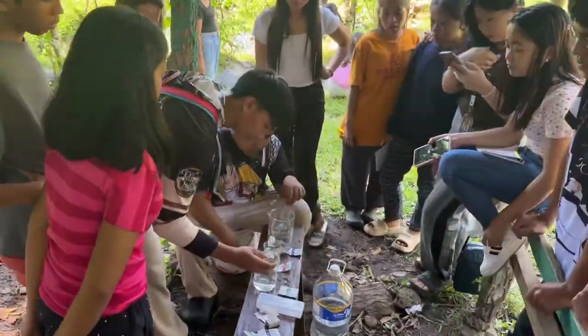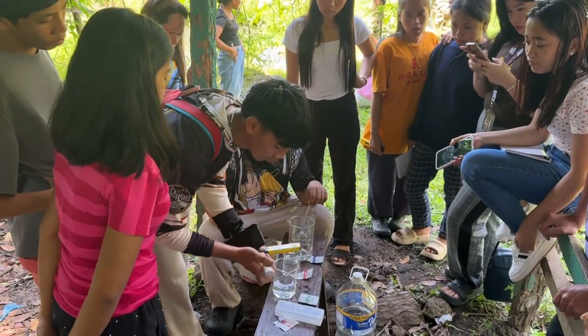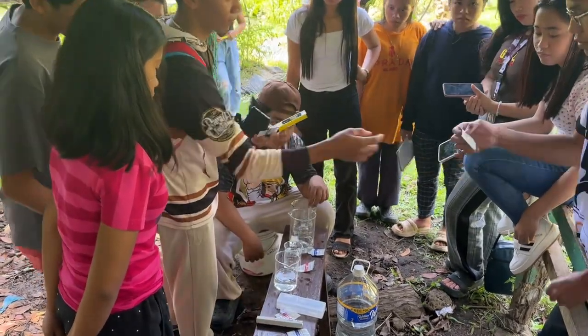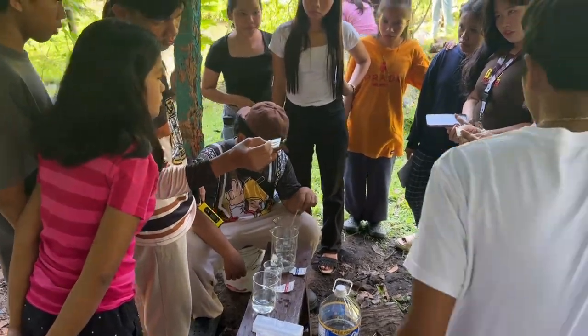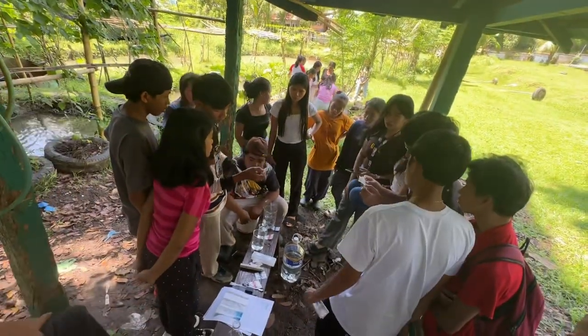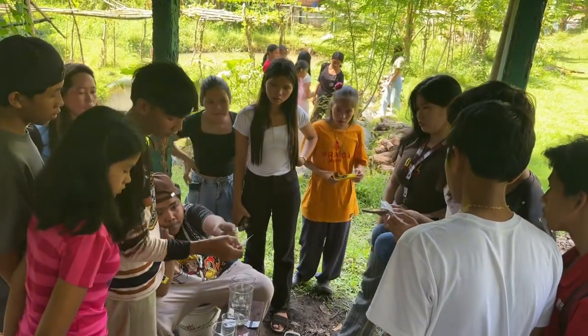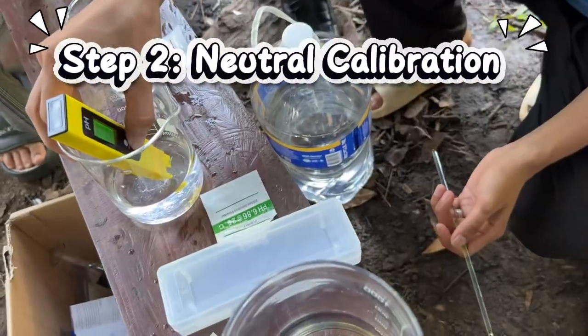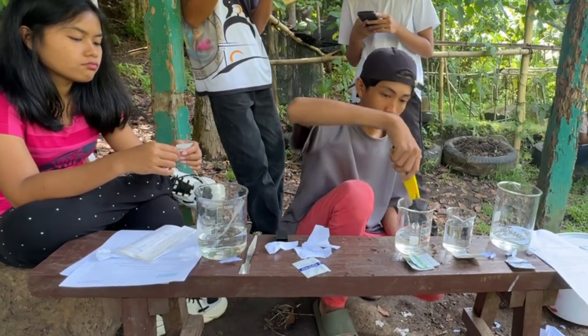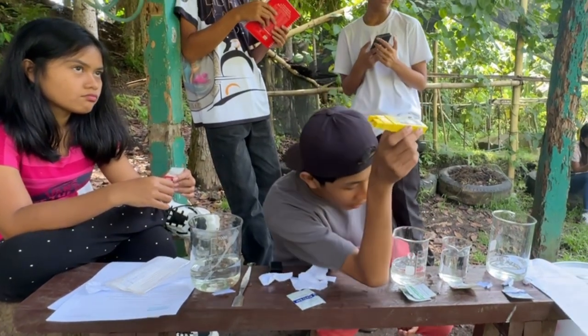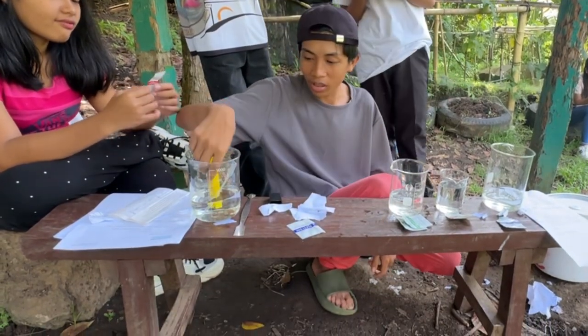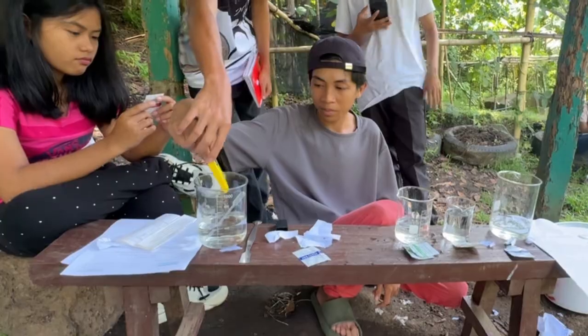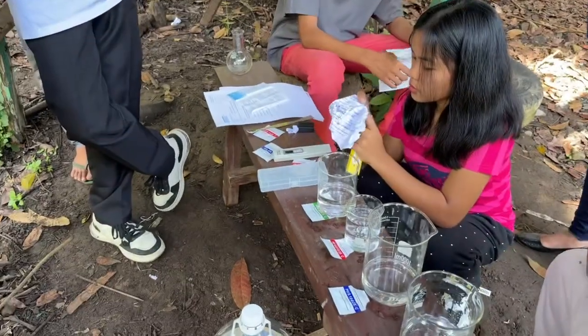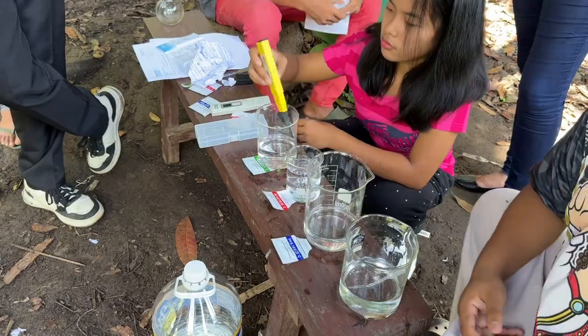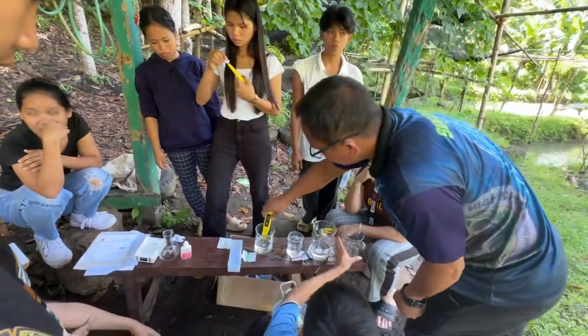Step-by-step calibration. Step 1. Turn on and rinse. Rinse the probe with distilled water to remove any old residue. Dab gently, never rub. Step 2. Neutral calibration. Green. Start with the neutral buffer, 6.86 or 7. Submerge the probe and wait for the reading to stabilize. If your temperature is not exactly 25 degrees Celsius, use the correction chart to confirm if the reading matches the adjusted pH.